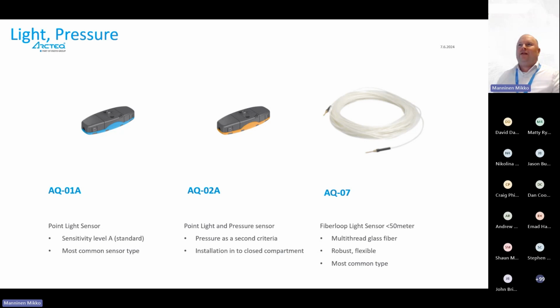And this pressure is something, if you think about the arc flash phenomenon, the light is actually the first thing that happens. When the arc flash occurs, there will be a flash first. Then there can be some decrease of the pressure for a very short time before the explosion actually starts. The delay of the pressure is typically seen to be about 6 to 7 milliseconds before the peak value. But it is one way to do it also, to monitor the pressure inside the panel. The sensors for the pressure are quick, are fast, but the actual pressure phenomenon is slow.